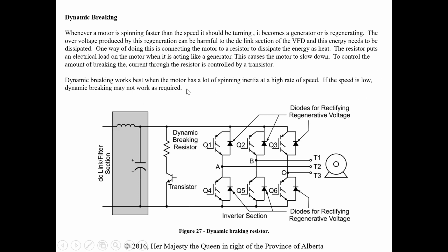Dynamic braking. Whenever a motor is spinning faster than the speed it should be turning, it becomes a generator, or is regenerating. The overvoltage produced by this regeneration can be harmful to the DC link section of the VFD, so this energy needs to be dissipated. One way of doing this is connecting the motor to a resistor to dissipate the energy as heat. So here's our dynamic braking resistor right here, before it goes to the DC link section so it doesn't damage it. This resistor puts an electrical load on the motor when it's acting like a generator. So we're just giving it a path to discharge, if you will.